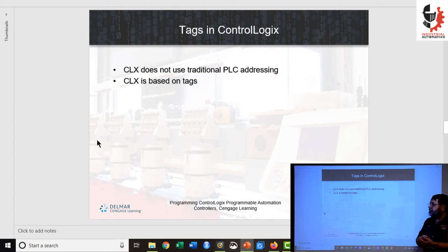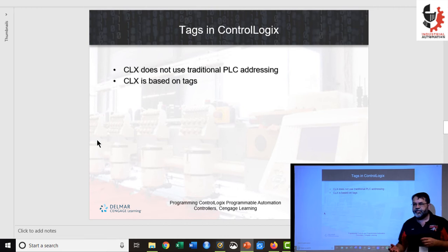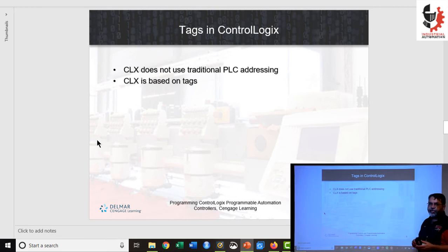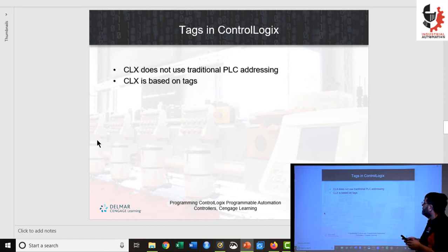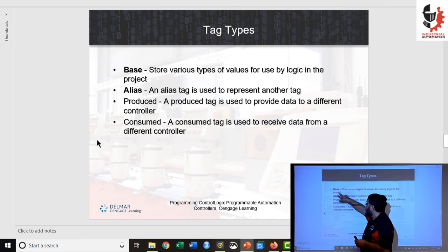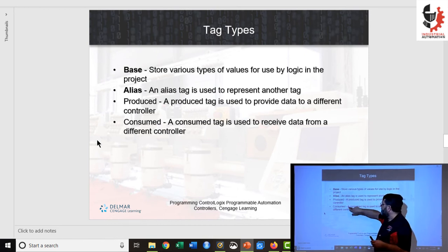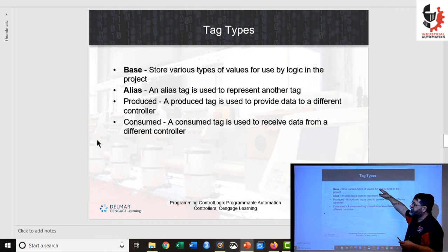Now I'll talk about tags. Control Logix — we use CLX as an abbreviation — is the PLC, and Studio 5000 is the software we use to program it. Control Logix does not use traditional addressing. The inputs and outputs have addresses but we don't use those when writing our logic. Instead we use tags, which is a simpler approach. There are four kinds of tags available in Control Logix, and we're going to focus on base tags and alias tags. The other two — produced and consumed — are more advanced and we won't use them.